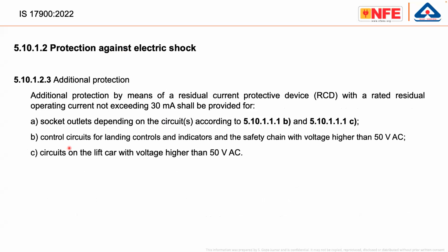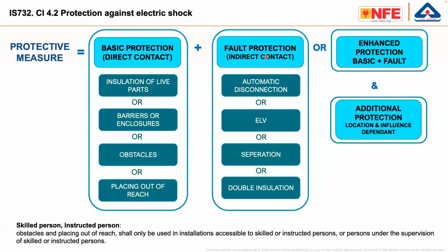But now the most important point is additional protection. Normal people, children, travel on the lift car. There are electrical wires, electrical light fittings and electrical appliances sometimes in the lift car. So those appliances, if the operating voltage is more than 50 volt AC, of course, most of the time it is 230 volt single phase supply, shall be protected with an additional 30 milliampere. Please read the sentence carefully. Additional protection. Let me show you the picture again. Basic protection, fault protection, additional protection. So three protective measures are required.